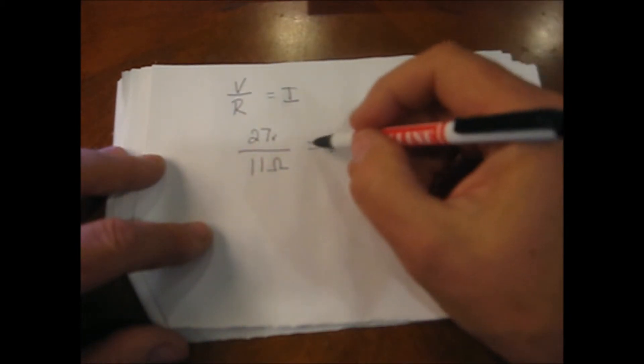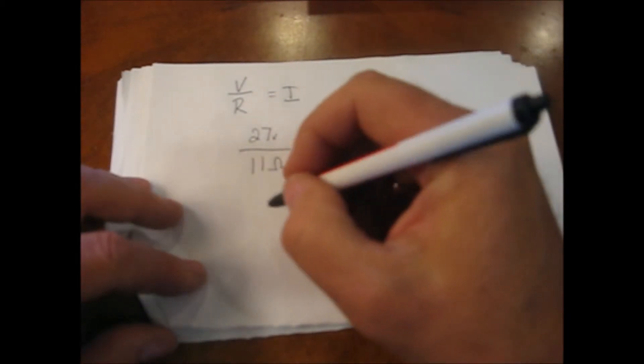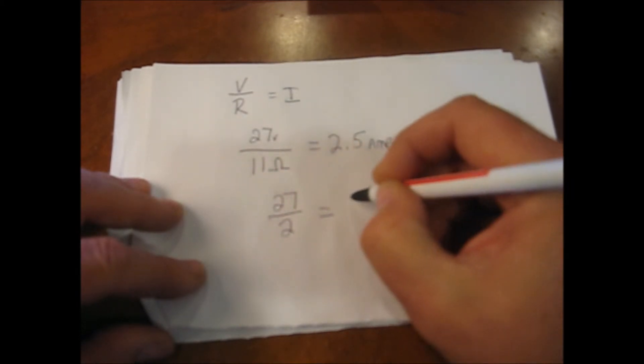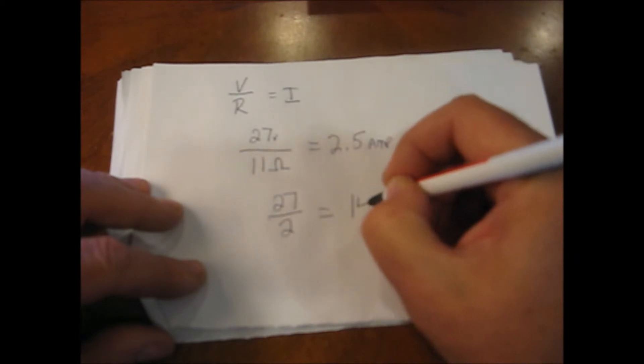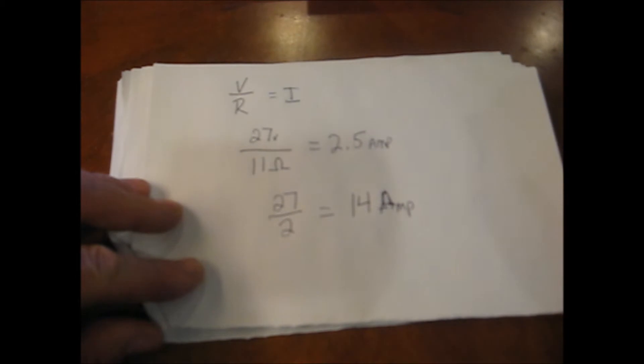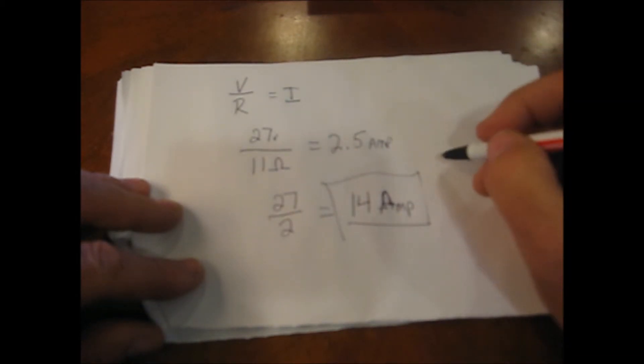If we had a short on there and maybe we're getting 2 ohms, what we might have is 27 divided by 2. And now we're looking at almost 14 amps. And that my friend will blow those little fuses in your furnace left and right all day long.